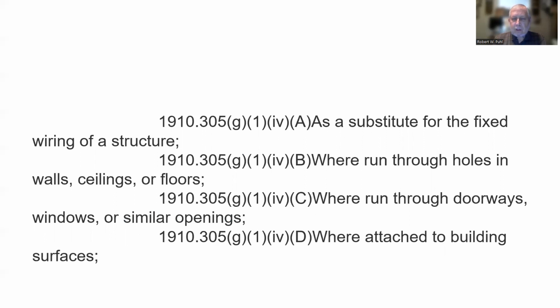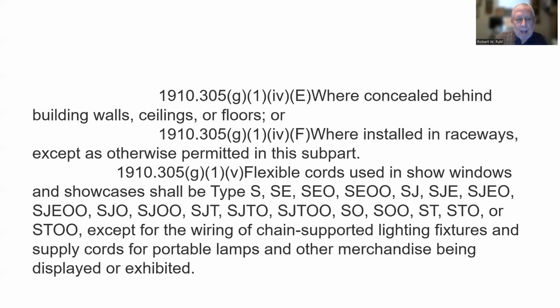Where run through holes in walls, ceilings, or floors. You can't run a flexible cord or extension cord through holes in walls, ceilings, or floors. Makes a lot of sense because it's ripe for abrasion or tripping or anything else. Where run through doorways, windows, or similar openings either. So you've got a window opening. You can't run an extension cord through a window opening either. Doors make sense. Guess what? When the doors open and close, they're going to pinch it. Where attached to building surfaces. They're not supposed to be attached to something. An extension cord is supposed to be temporary. Where concealed behind building walls, ceilings, or floors. So if you can't see a part of it, how do you know it's going to be any good, right? Or where installed in raceways except as otherwise permitted in this subpart.